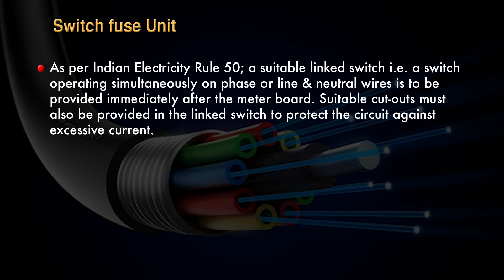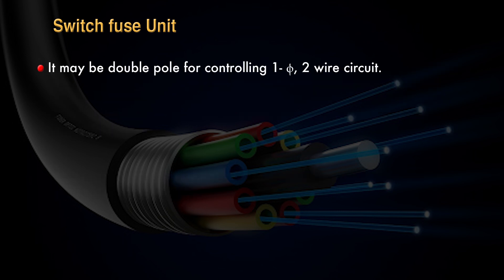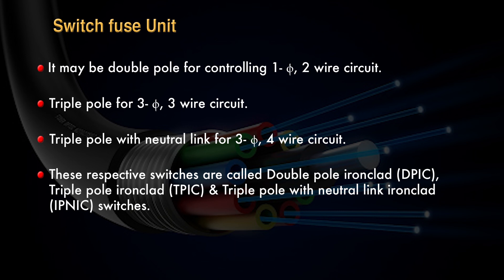As per Indian Electricity Rule 50, a suitable linked switch — operating simultaneously on phase or line and neutral wire — must be provided immediately after the meter board. A suitable cutout must also be provided to protect against excessive current. The combined linked switch and fuse unit is called a Switch Fuse Unit, also known as an Iron Clad Switch. It may be double pole (DPIC) for single phase 2-wire circuits, triple pole (TPIC) for 3-phase 3-wire circuits, or triple pole with neutral link (TPNIC) for 3-phase 4-wire circuits.